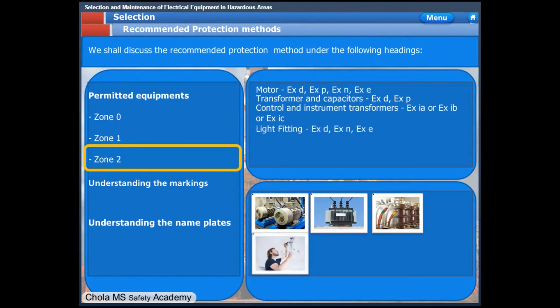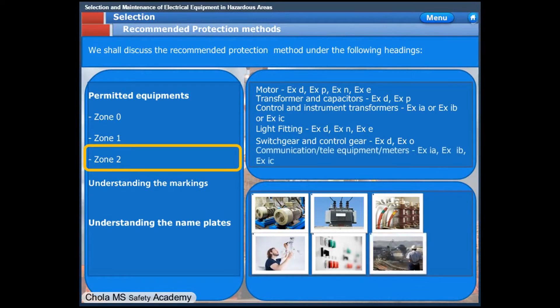Light fittings in Zone 2 shall be non-sparking or increased safety type. Flame-proof fittings may also be used but are not mandatory. Switchgear and control gear shall be flame-proof or oil-immersed type. Communication and metering equipment may be intrinsically safe Ex ic type. Portable hand lamps shall be Ex ic type.